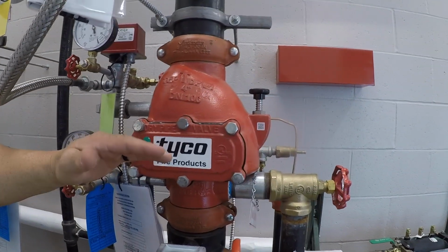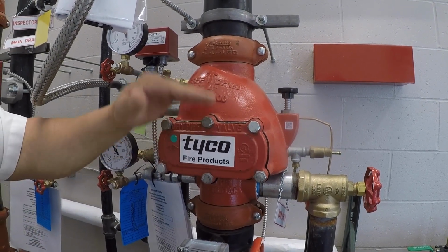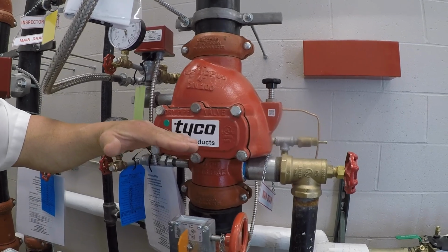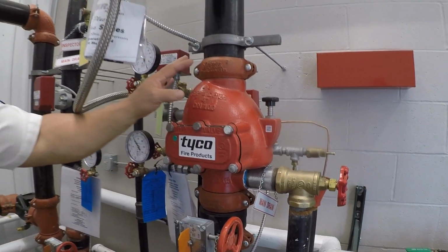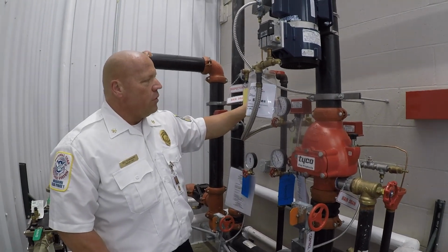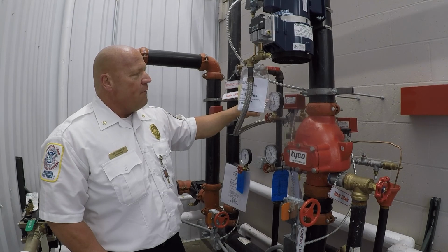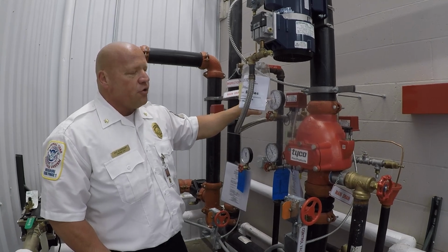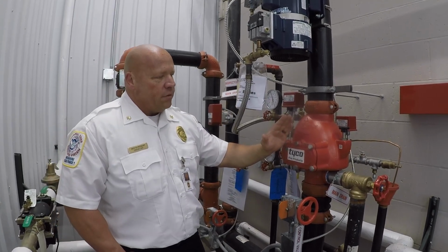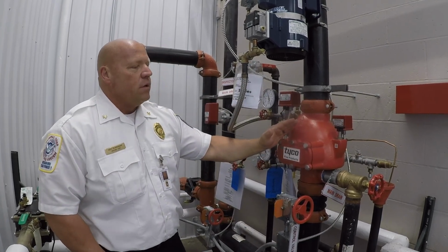The way they do that is strictly, it's a clapper type valve. So there's a little bit of water on here with air pressure holding that valve closed. Once the sprinkler head activates on the dry system, the air pressure will be released out of that sprinkler head. And once it hits about 15 pounds of air pressure, this valve will open and water will flood the entire sprinkler system on the dry side.